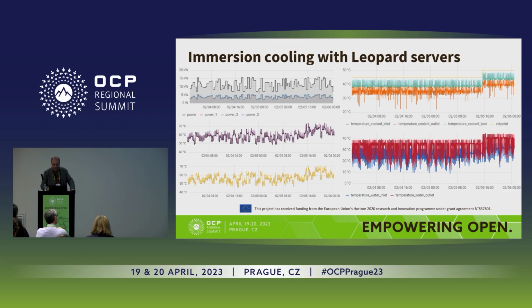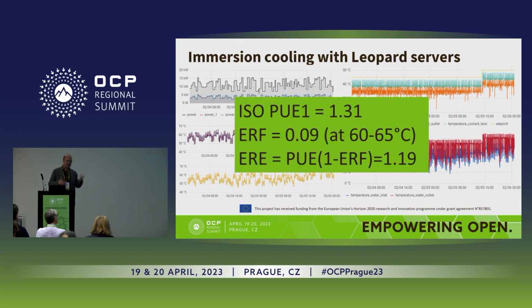I can't tell you much more about this, but it actually isn't running on electricity. It's running on biogas. That's another story. But because I keep getting up and talking about PUE and ERF, I changed the slide at the last minute. I thought, what is the ISO PUE of this? It's actually 1.31. It's an ISO PUE because it's annualized, it's over 1 year. And it's PUE 1 because it's the power that's measured at the UPS, or we don't have a UPS, but at the point of delivery.